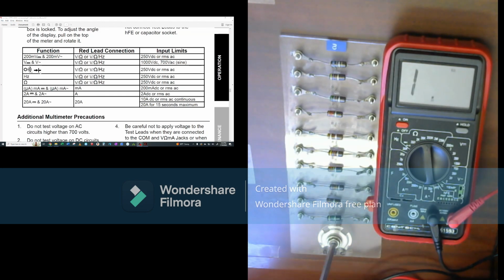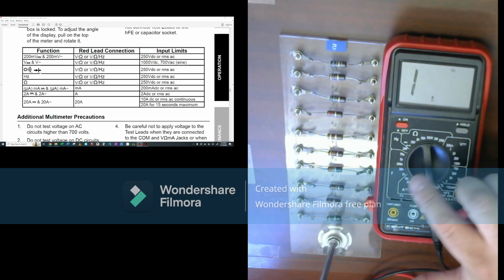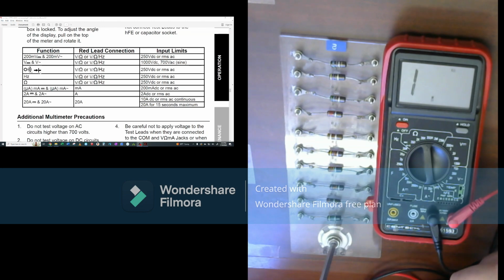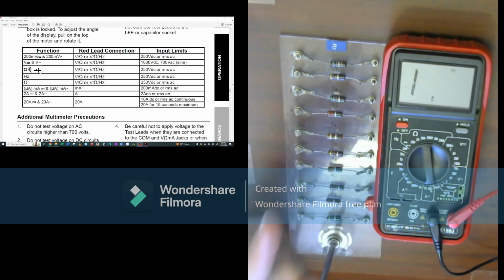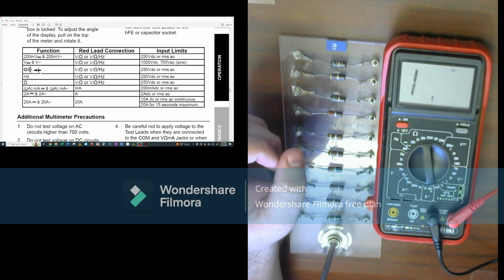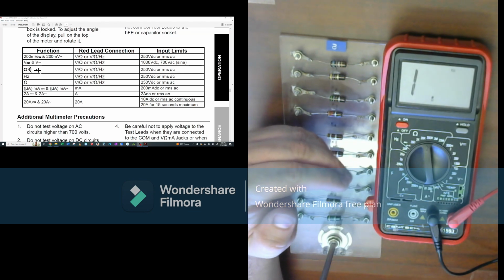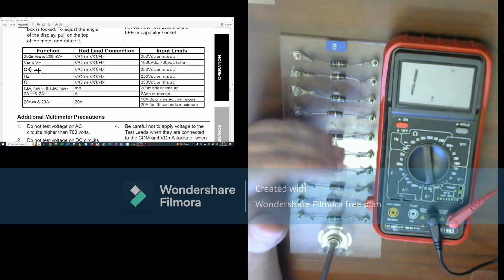Remember in the instructions when we were talking about the overview, if we don't know what the value is, we want to start high and walk it down until we get a value that's close to the maximum. We do that for two reasons. Number one is so that we can get an accurate reading. If we have too high or too small of a scale, the accuracy of what we're trying to measure is going to change with it. So that's the first reason, our accuracy.